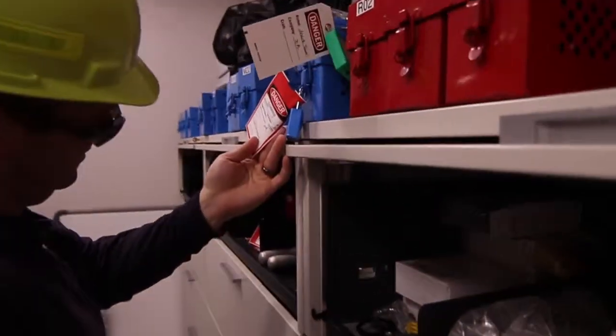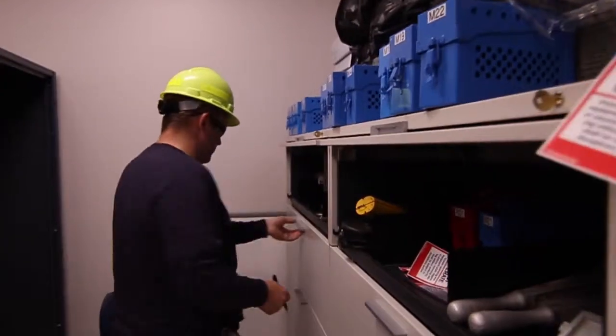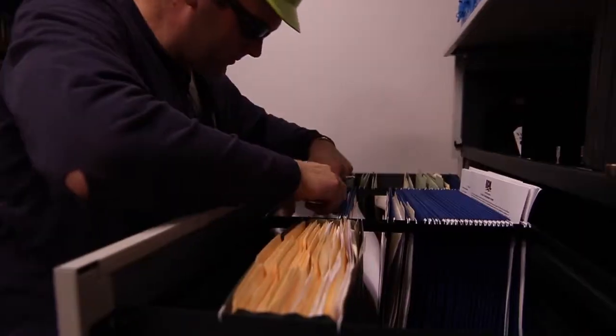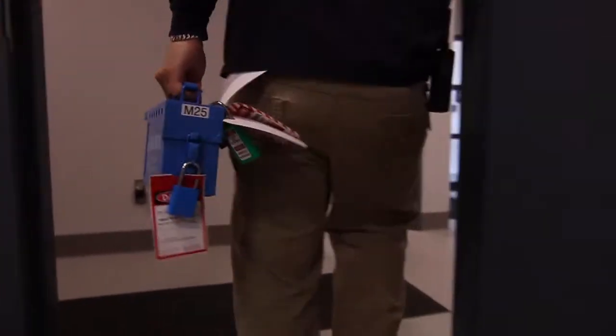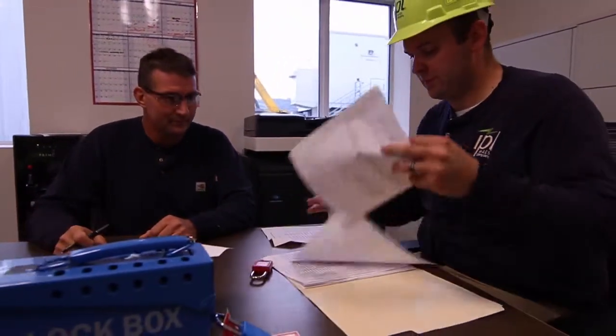The Eagle Valley Plant Hazardous Energy Control Program is commonly referred to as the Lockout-Tagout Program. Additionally, clearance permits are used to track both equipment isolation information and authorized personnel working on isolated equipment. A clearance permit is documentation combined with a method to properly isolate equipment from hazardous energy.